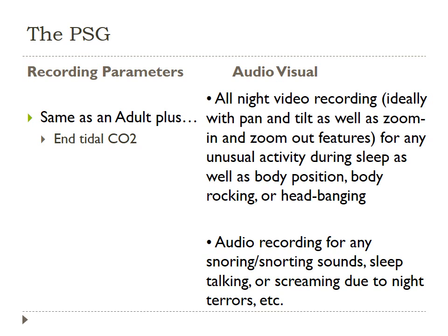As far as the polysomnogram itself, the recording parameters are going to be exactly the same as adults, plus the addition of end-tidal CO2. For audio-visual equipment, we want all-night video recording, ideally with pan and tilt as well as zoom in and zoom out features. This is used for any unusual activity during sleep, body position, body rocking, or head banging.